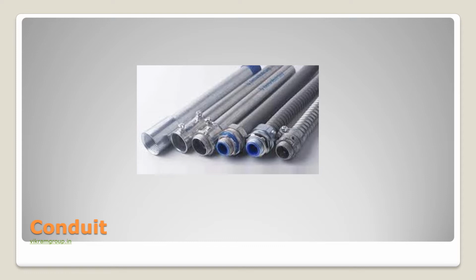On the far left, we see what's called rigid conduit, and it's really just like a pipe. You know, if you pick it up and feel it, it looks like a galvanized pipe. It feels like a galvanized pipe. It's got a thick wall. You can physically thread the pipe just like you could a piece of water pipe, as an example, and it provides really good protection. It is, however, difficult to run, and in a lot of cases we don't need anything quite that robust. So we can use EMT, or electrical metallic tubing.